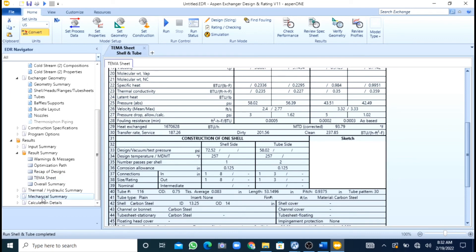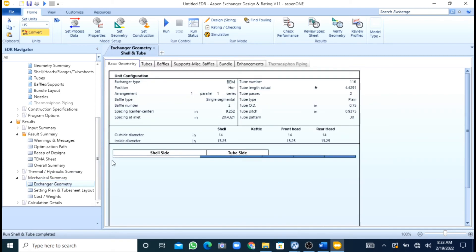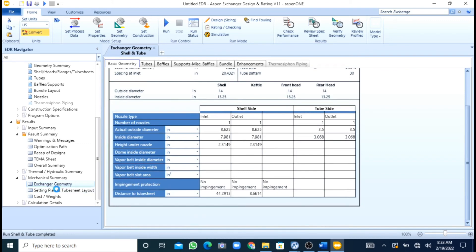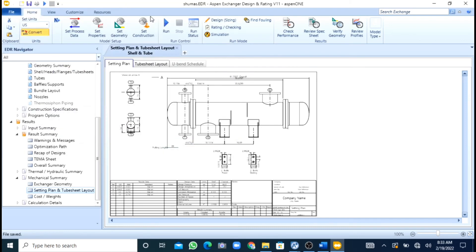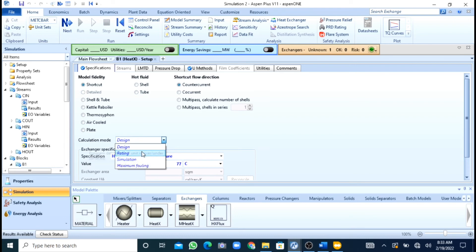Now I will save this and we will move to our simulation again for the rating end. I will select here as rating, and then select shell and tube. I will press 'Specify Exchanger Geometry' because I have designed a heat exchanger. I will import my EDR file — for this I will press the browse button. Now you can see that was my EDR file, and then I will press convert. Now I will change it to rating and press the EDR browser.